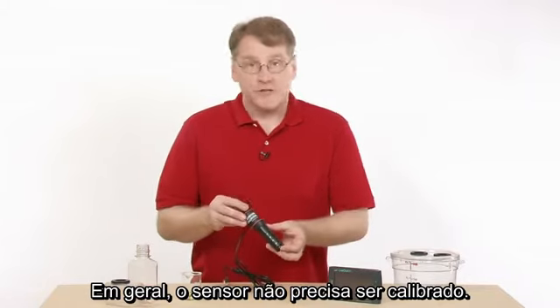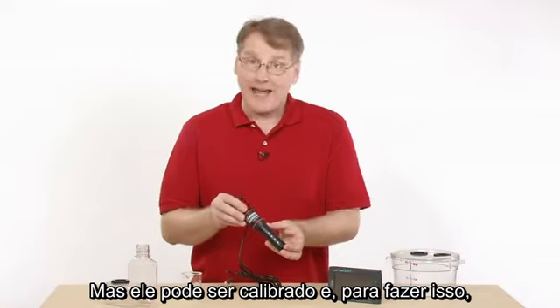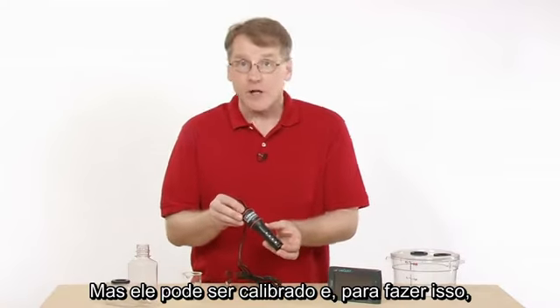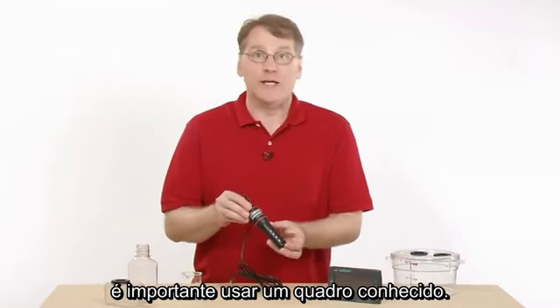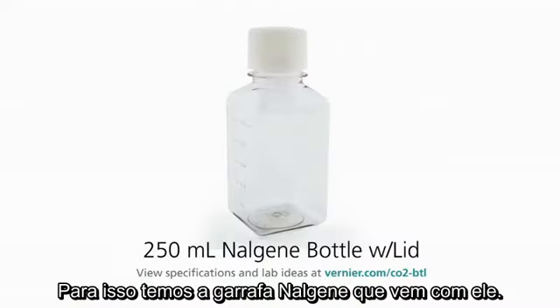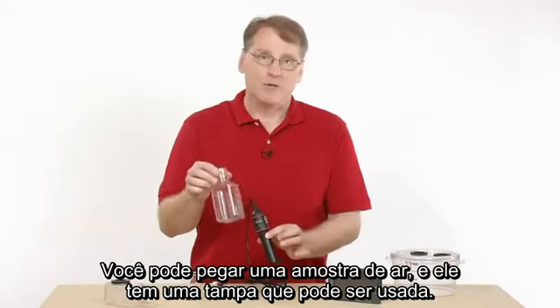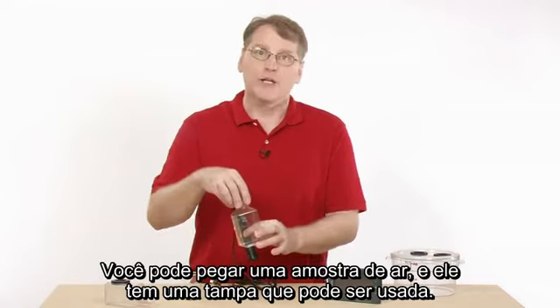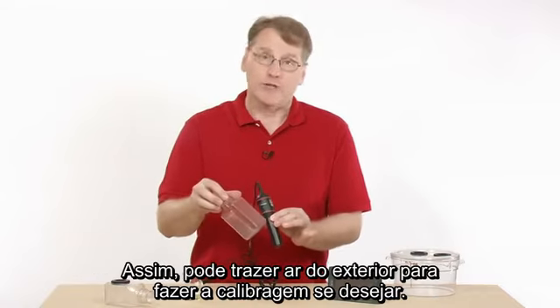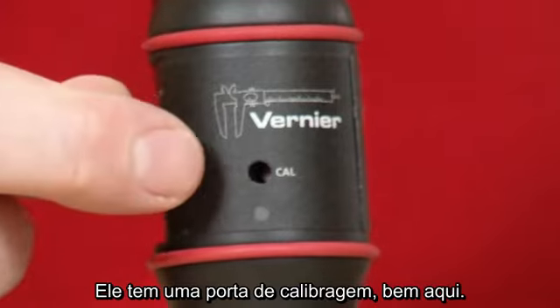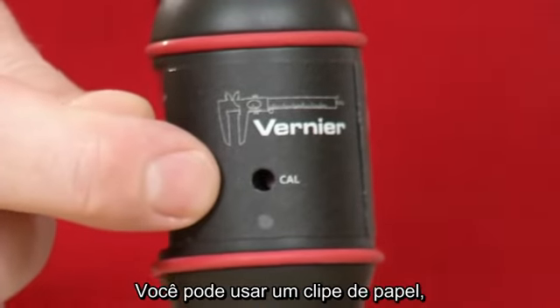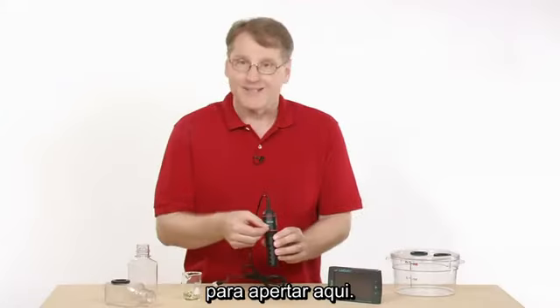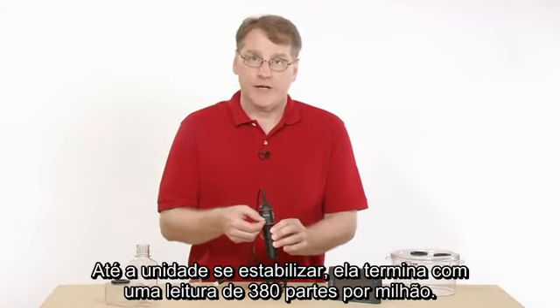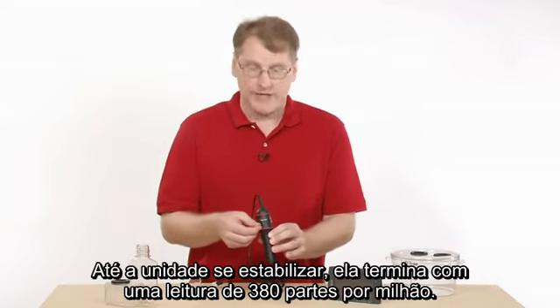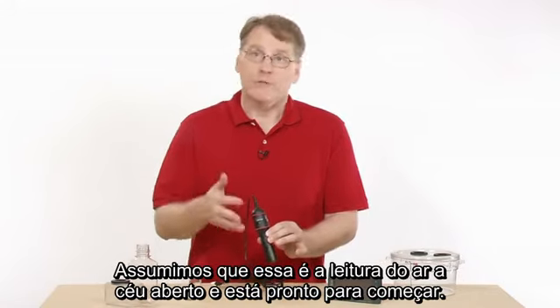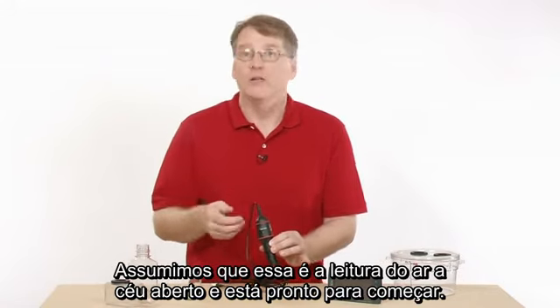The sensor in general doesn't need to be calibrated, but you can. To do the calibration, it's important that you put it into a known condition. Take the Nalgene bottle that comes with it, and you could collect a sample of air, and it has a lid that you can put on it, and you could bring it back in and then do the calibration that way if you wanted to. There is a calibration port right here, and you can take maybe a paper clip and press down on this until the unit stabilizes. It'll end up with a reading of 380 parts per million. Then we assume that's what it is outside in open air, and then you're good to go.